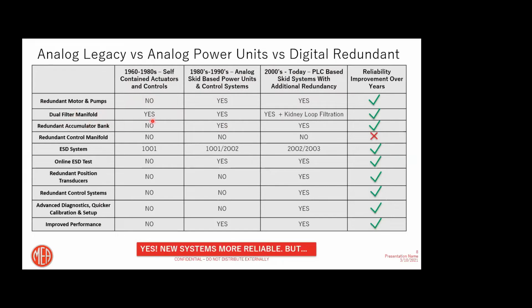So if you now have a pump failure, you can go back and operate the other one. Dual filter manifolds: the older units had one, while current units have a kidney loop filtration system, one of the newer ones. Yes, we improved fluid cleanliness, for sure, a reliability improvement. Redundant accumulator banks, an additional improvement. Current units have numerous accumulators, so if one fails, the other comes back online and operates well, definitely a reliability improvement.